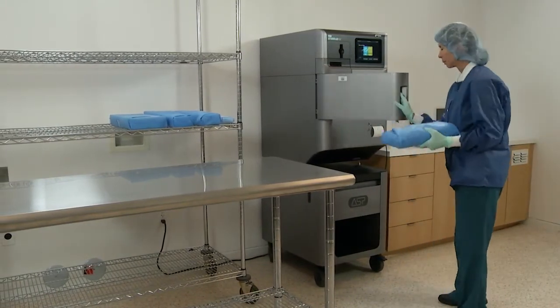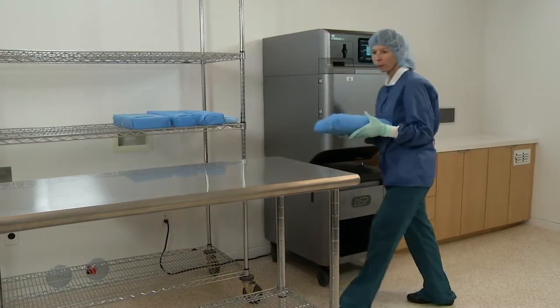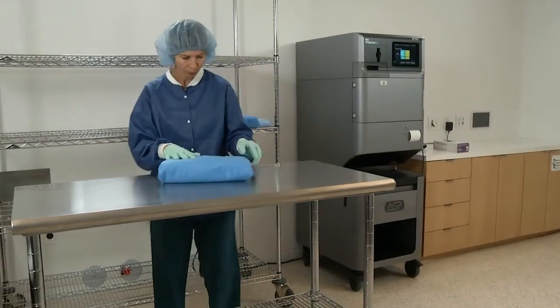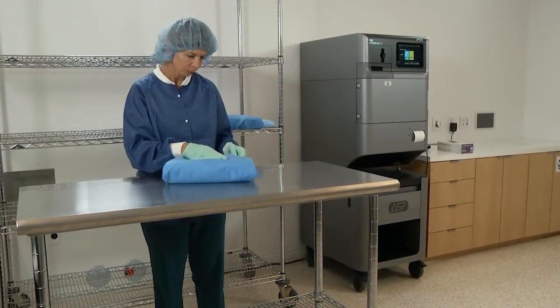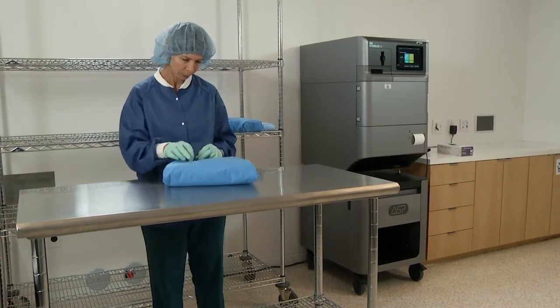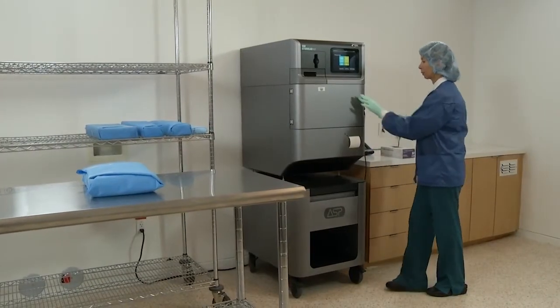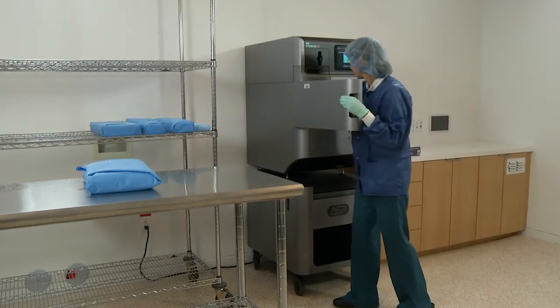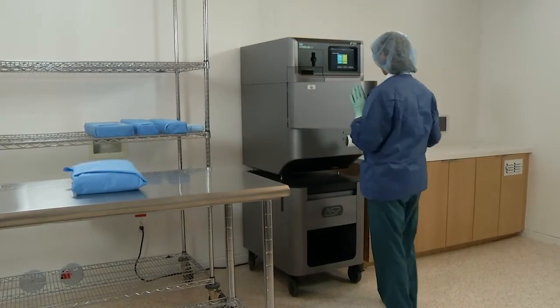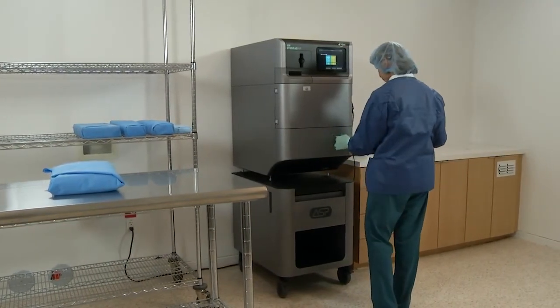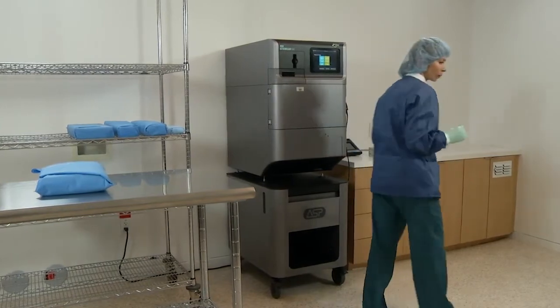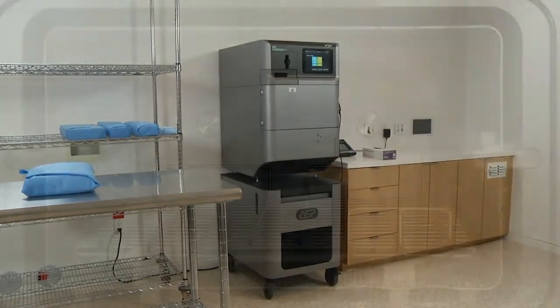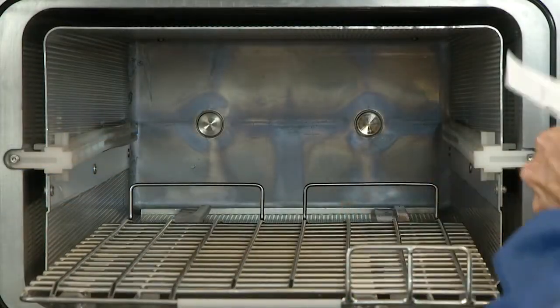Loads from canceled cycles should be rewrapped using new packaging materials, STERRAD chemical indicator strips, and STERRAD SealSure chemical indicator tape. If a biological indicator, or BI, was used in the canceled load, the previously used BI must be disposed of per your hospital or healthcare facility's policy, and a new BI must be placed in the chamber before restarting.